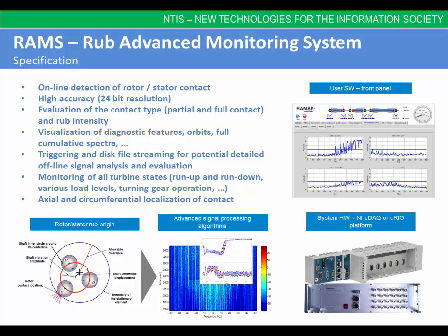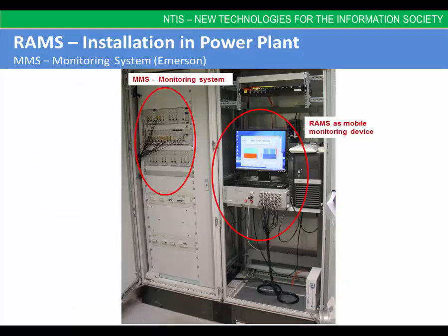The RAMS localization function is capable of both axial and circumferential determination of the contact point. The RAMS uses existing sensors which are the standard equipment of the turbine monitoring system. In most cases the buffered outputs from the installed turbine monitoring system are used as RAMS inputs. For each measurement plane a couple of relative shaft vibration sensors and one absolute bearing vibration sensor is used.